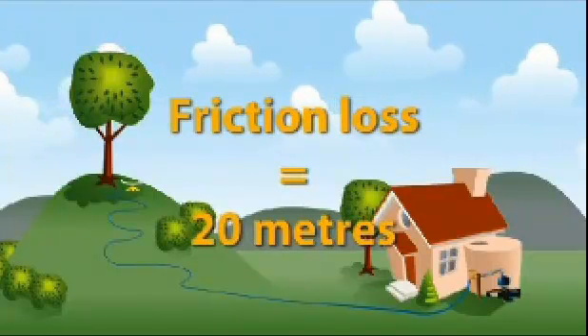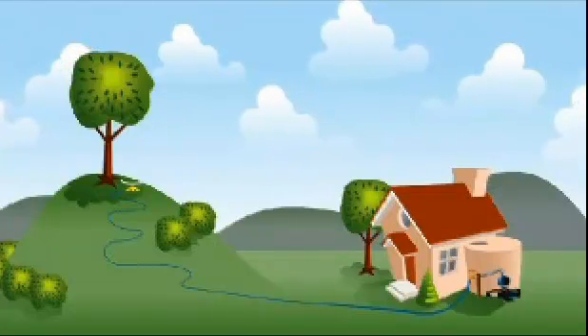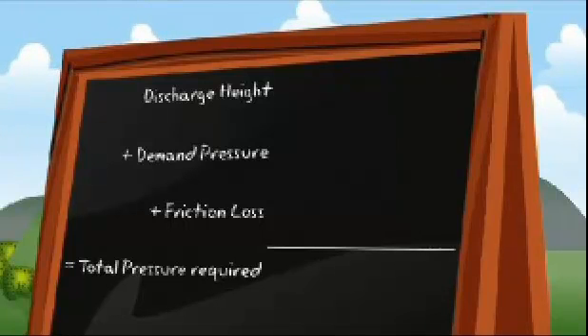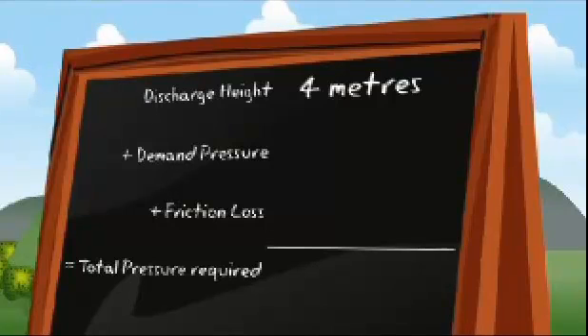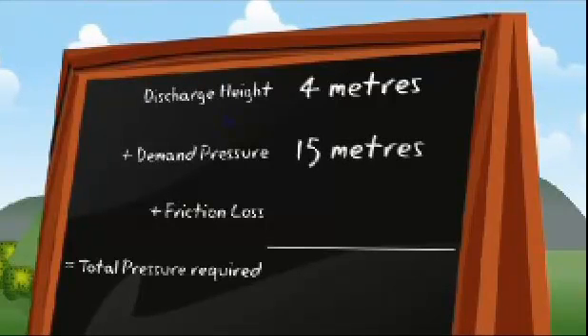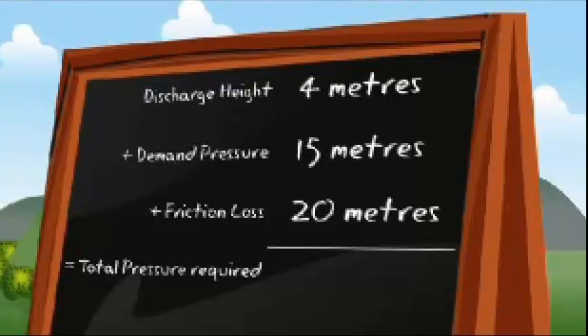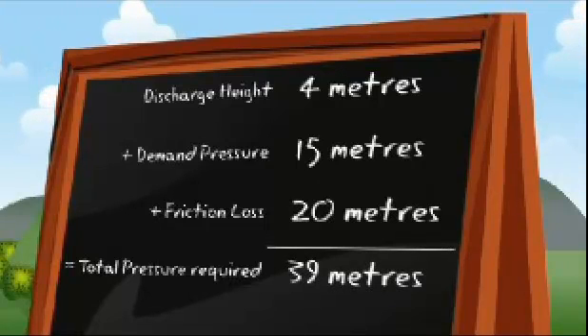The next step is to calculate the total head or pressure the pump will need to accommodate. We know that the discharge point is 4 metres above the pump and the demand pressure of the sprinkler is 15 metres or 150 kPa. We have just calculated that the friction loss will be 20 metres. Add these three amounts together and we have the total amount of head or pressure required, in this case 39 metres.